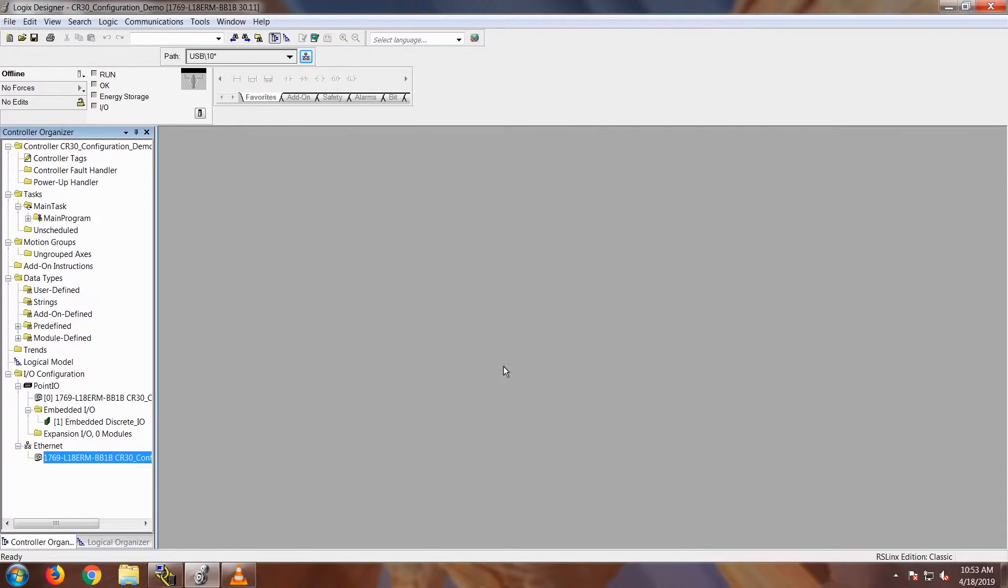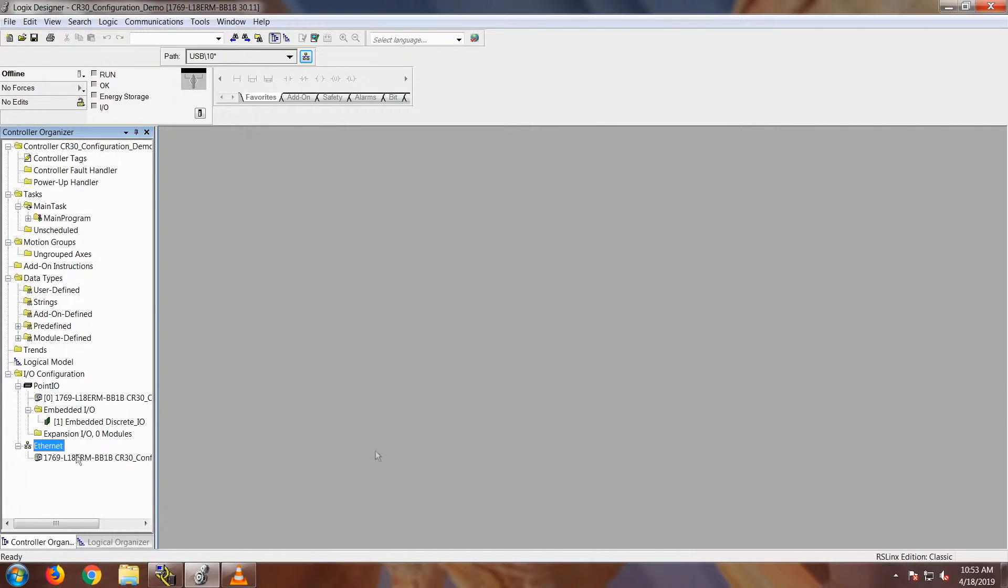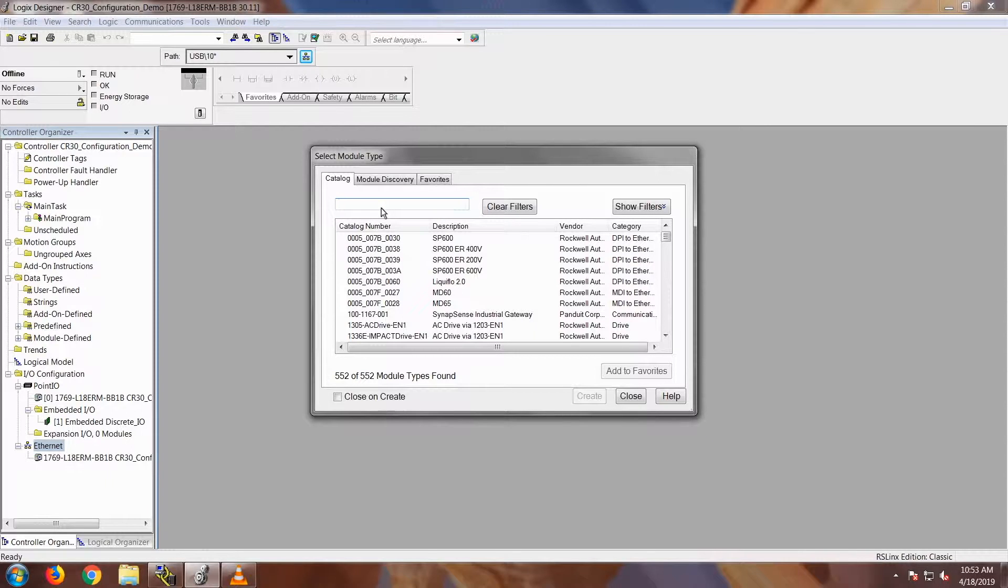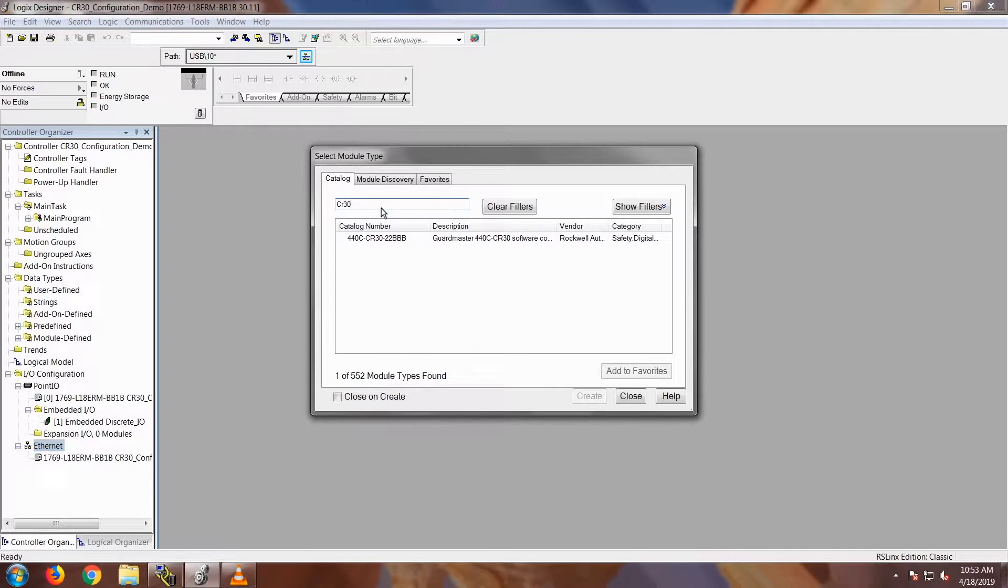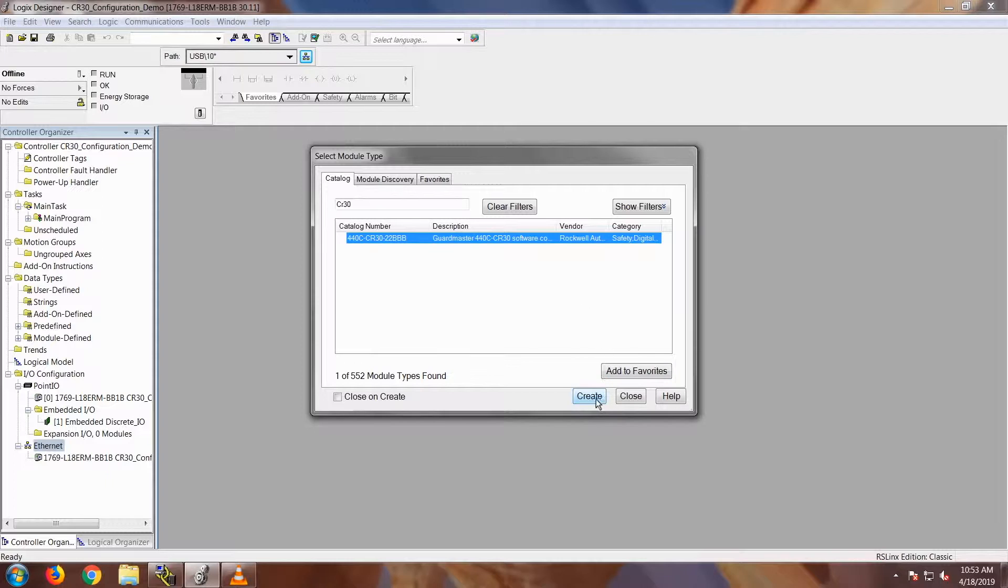I have a program already set up. First thing is you want to right click on the Ethernet because we have to add the CR30 into the IO tree. Right click on the Ethernet and select New Module. When the text box comes up, go ahead and type in CR30 and that will bring up the 440C CR30 add-on profile that you can add into the IO tree and then click on Create.